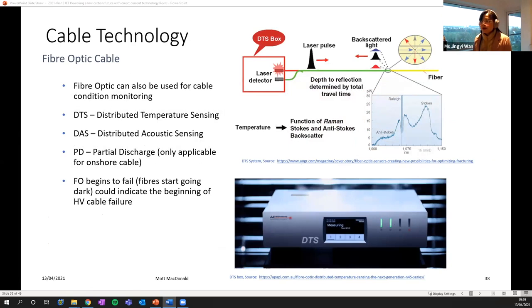Staying on the theme of fiber optics, one advantage of having the FO unit is the ability to be used for cable online condition monitoring. The technology includes DTS, which is distributed temperature sensing, and DAS, distributed acoustic sensing. One pre-fault condition of an HV cable fault is that we might find all of the fibers start to go dark first. This is normally a good indicator of something wrong with the cable, and it gives us the chance to react or pre-act with some maintenance measure to avoid the significant cost of a high voltage cable fault.